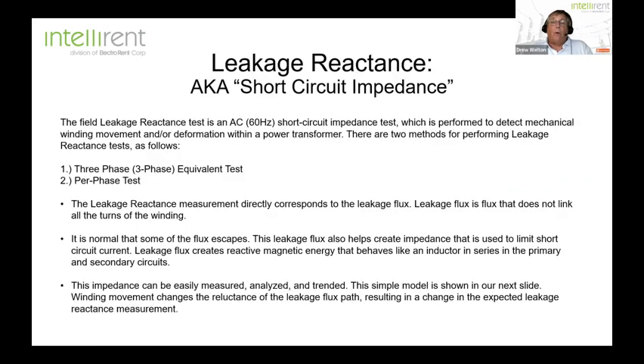Now, the other test you can perform, and this is much simpler, is leakage reactance, otherwise known as short circuit impedance. And I know that if you work for a contract testing company, and I know because we rent to them all the time, we'll rent a power factor test set, and then every once in a while, the leakage reactance accessory with it. And sometimes if you ask a field tech, well, why do you need to do a leakage reactance test? The response might be because my customer wants it. Well, I have an old saying that says you really shouldn't do anything unless you understand why you're doing it. And it's important to understand why and when to do a leakage reactance test.